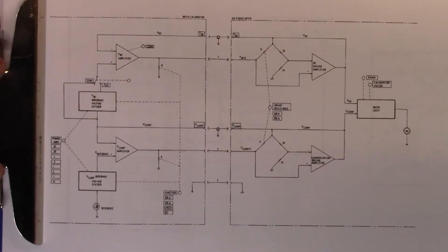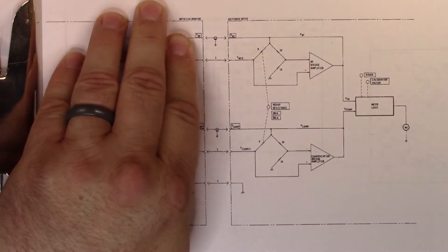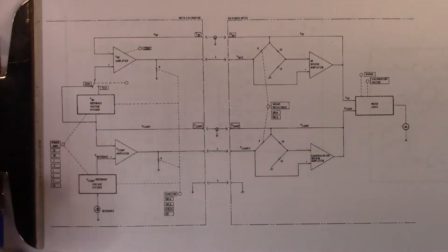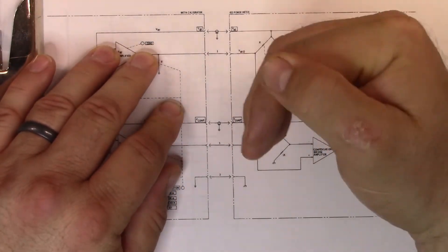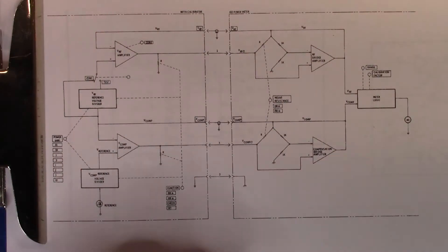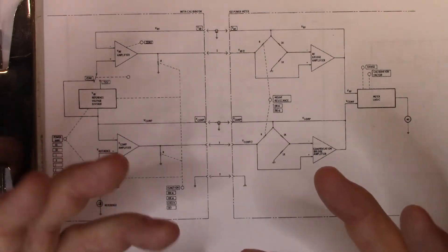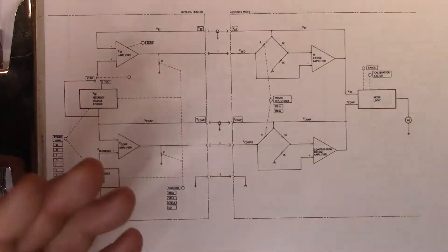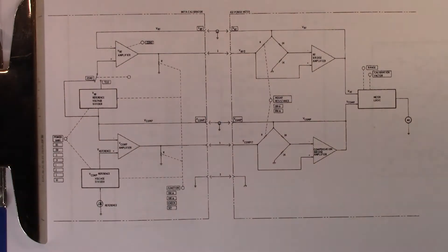Let me just zoom in a little bit. And what you can see here is this is the power meter. And the power meter has a set of bridges that it uses the thermistor to be the other half of the bridge. And what it has is it has an RF input, which is the part of the thermistor where the RF is coming in, and that has a VCOMP, which is to compensate for the thermal noise and the temperature. So the RF comes into one of the thermistors, and the other thermistor is mounted very close so that it gets the same thermal experience, but it doesn't have to have the, it doesn't get the RF. Now, the 432A can take those signals, chop them up, work with them a bit, and basically it gets rid of the thermal noise.